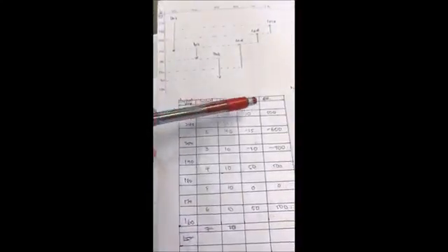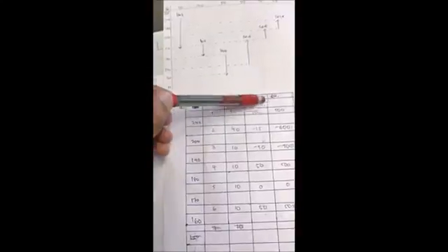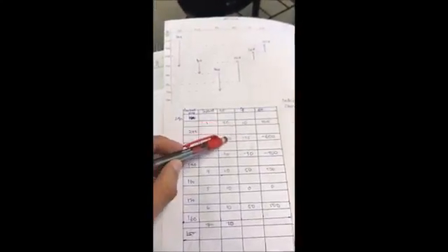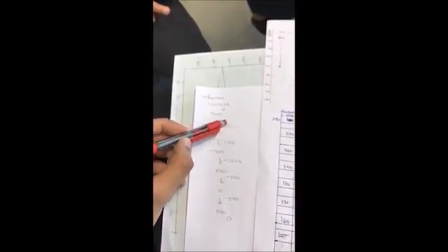Now once we have this, we will then move on to our cascade. For the cascade, what we want to do is just add or subtract the delta H for every single temperature interval. In this case, our first temperature interval has 500. Then the next temperature interval goes to negative 600. Because we start with 0 and we add 500 kilowatt of enthalpy, you get a remainder of 500. So this is what we add, and this is what remains in the system.